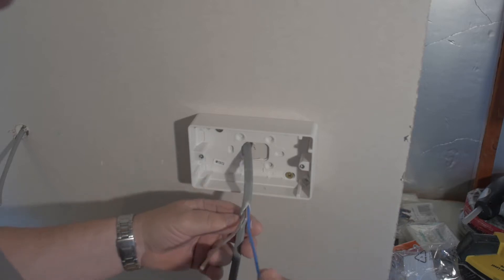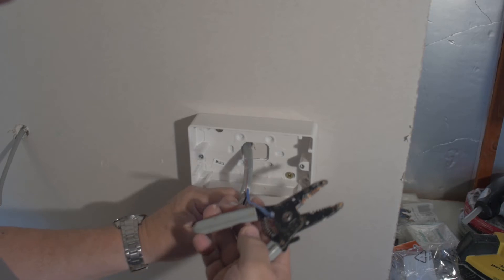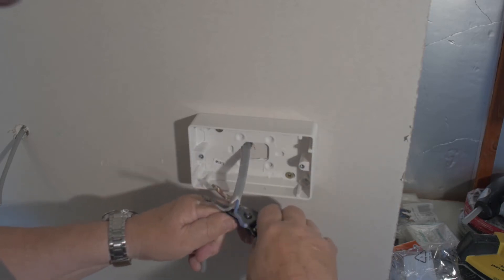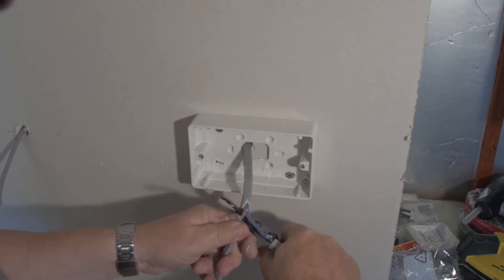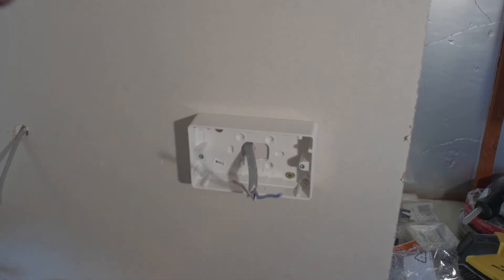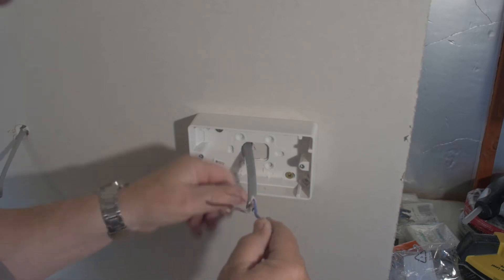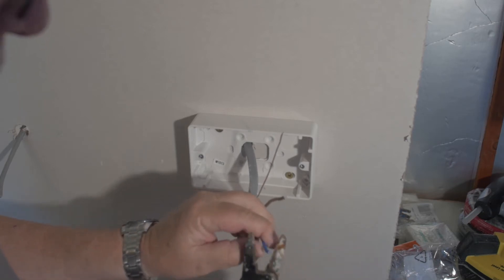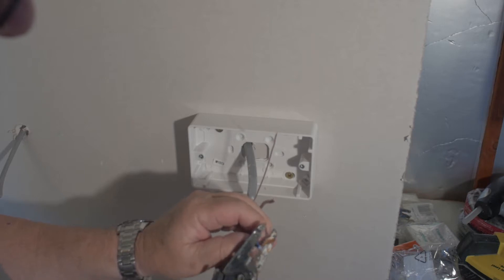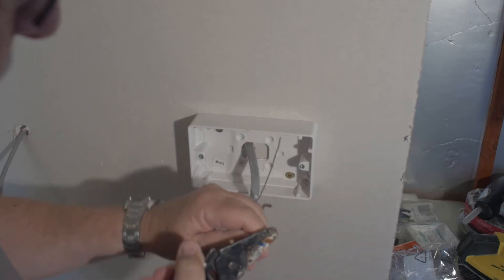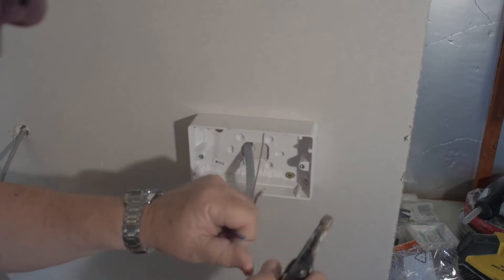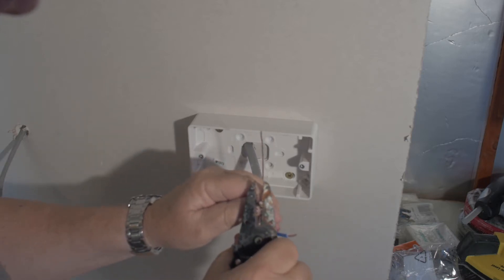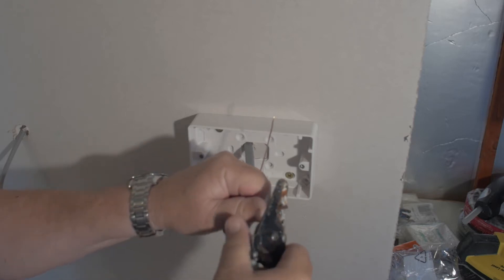So the next thing to do is trim away the excess outer cable. You can do that easily with your cable snippers and cutters. So just cut that back and remove that piece. The next thing we do is we need to take off 10 millimeters of cable approximately and just remove that from the actual cable. That leaves... same with the brown.